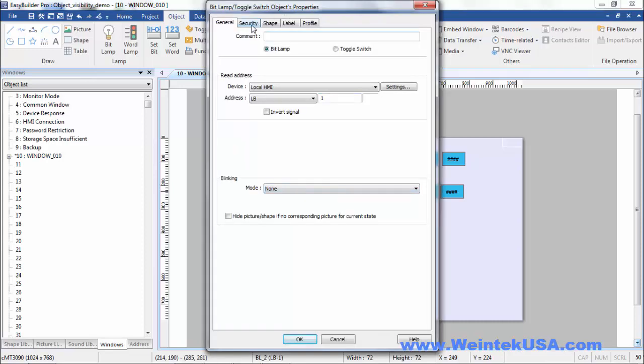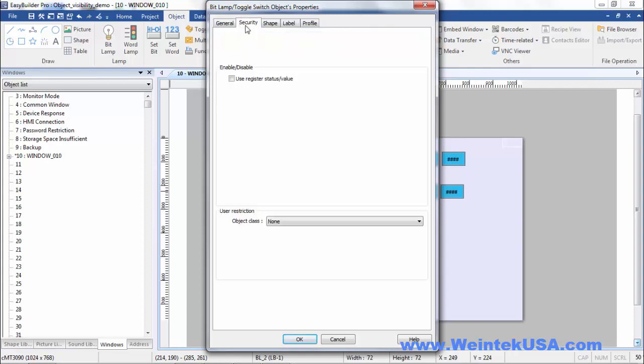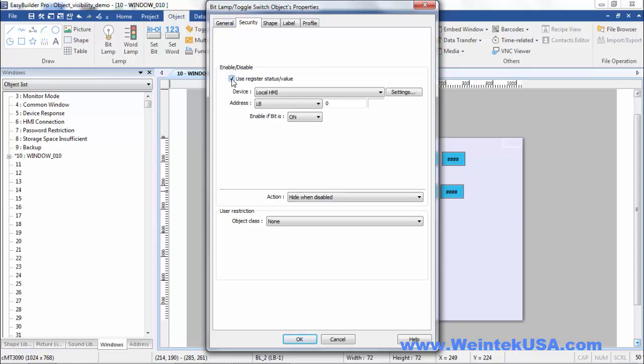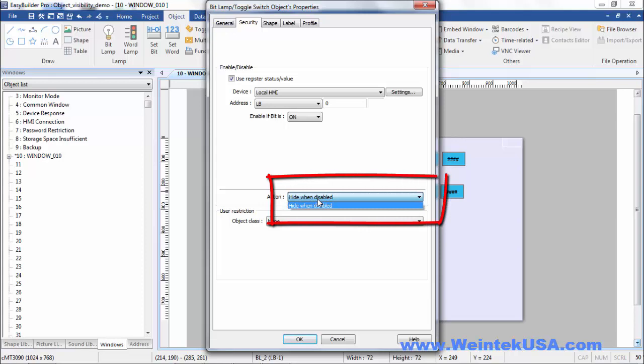Now within an object we have the security tab. And in EasyBuilder Pro we call it enable disable. Depending on the object, we've got different selections available. We can either disable it or hide it in some objects, but in the bit related objects it's basically hide when disabled.